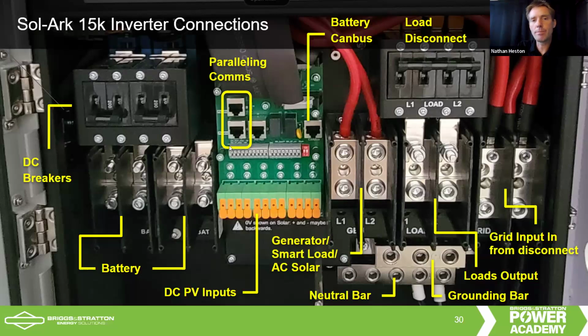You've got paralleling communication. So if you're paralleling multiple inverters, you would come out of inverter 1 into inverter 2, out of inverter 2 back to inverter 1. So you've got closed loop communication there. Battery CAN bus. This is where the battery communicates to the inverter. So that's where you would plug your battery Ethernet comms cable in. And we do have a dongle that's included with our battery stack that you would use to come into that CAN bus port. Then you've got the generator or the smart load output.